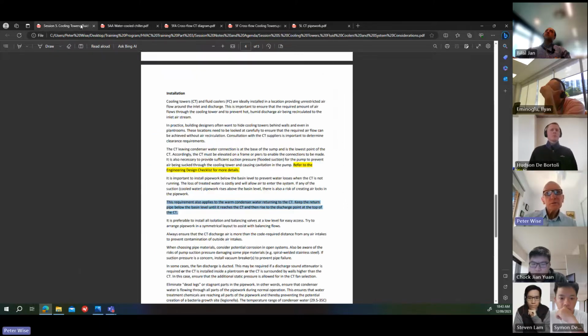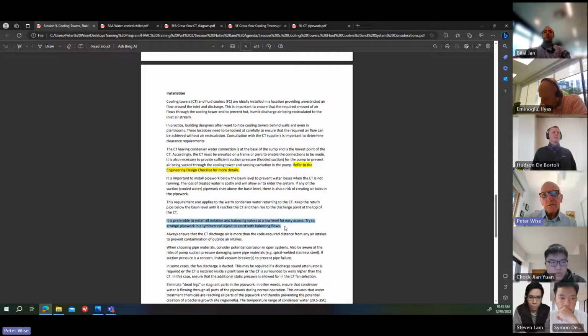So these things are just important to be aware of and make sure you implement them when doing your design. It's also preferable to install all the isolation and balancing valves at low level for easy access, so you don't have to climb up to the top of the cooling tower to fiddle around with valves to try and get the balance right. And try to arrange the pipework in a symmetrical layout to assist with balancing the water flows. You want to get the same flows going through each tower when it's operating to get good distribution.